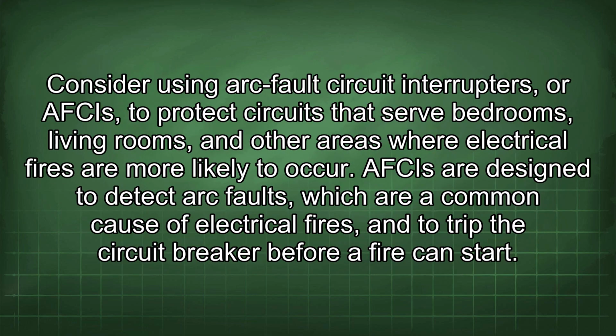Consider using arc fault circuit interrupters, or AFCIs, to protect circuits that serve bedrooms, living rooms, and other areas where electrical fires are more likely to occur. AFCIs are designed to detect arc faults, which are a common cause of electrical fires, and to trip the circuit breaker before a fire can start.